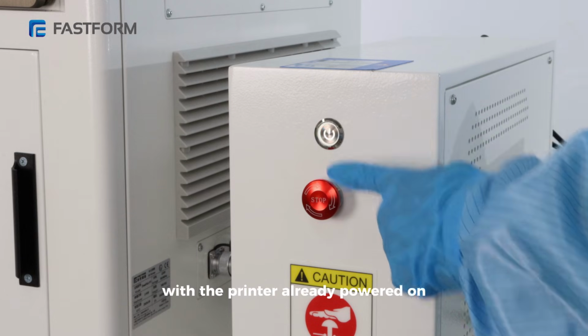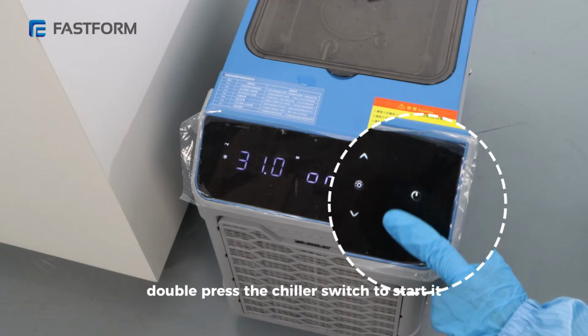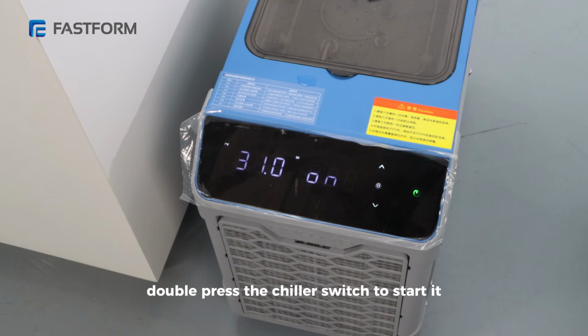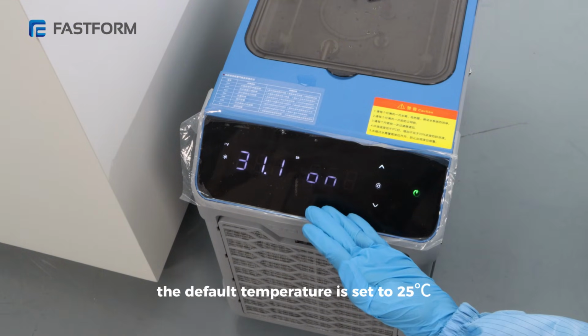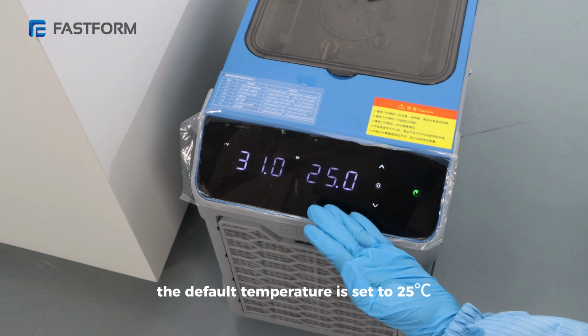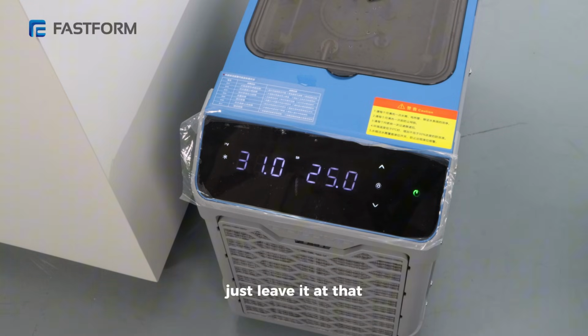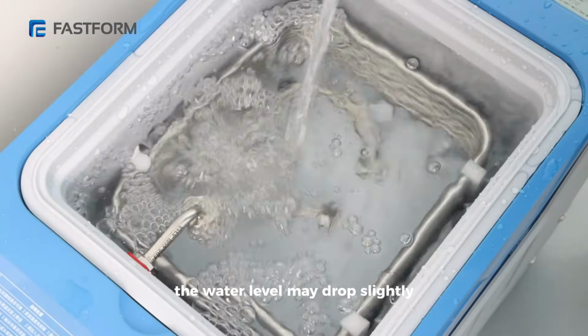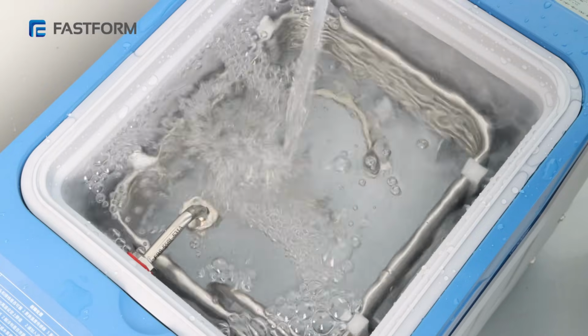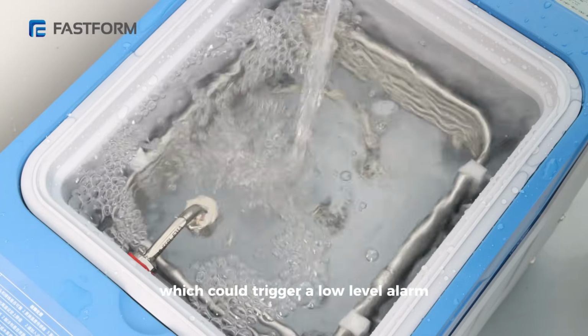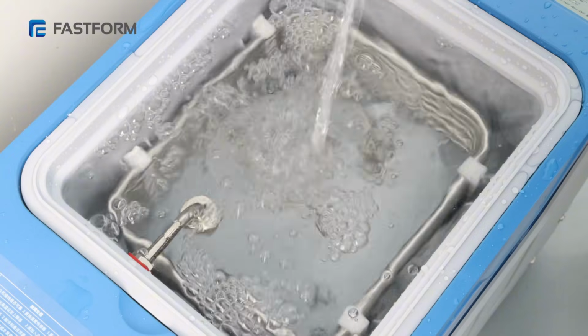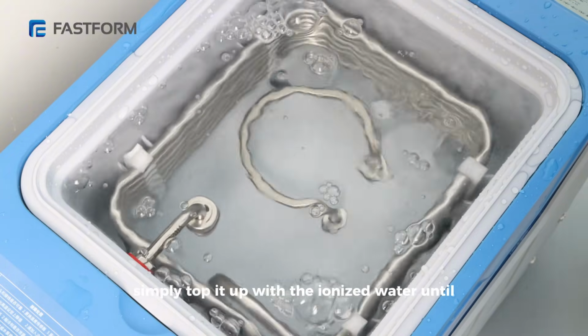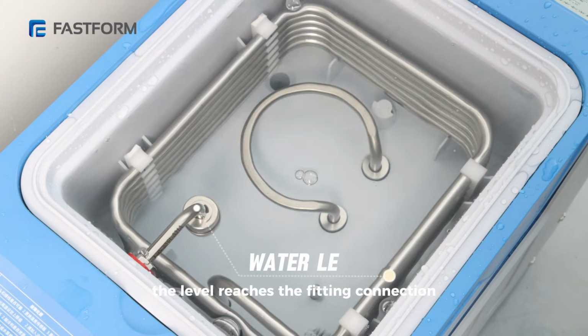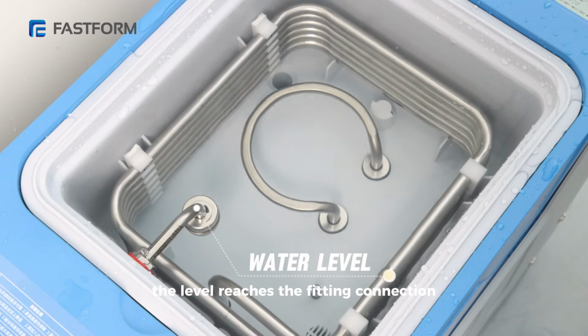With the printer already powered on, double press the chiller switch to start it. The default temperature is set to 25 degrees Celsius. Just leave it at that. Once running, the chiller will start circulating water through the printer. The water level may drop slightly, which could trigger a low-level alarm. If that happens, simply top it up with deionized water until the level reaches the fitting connection.